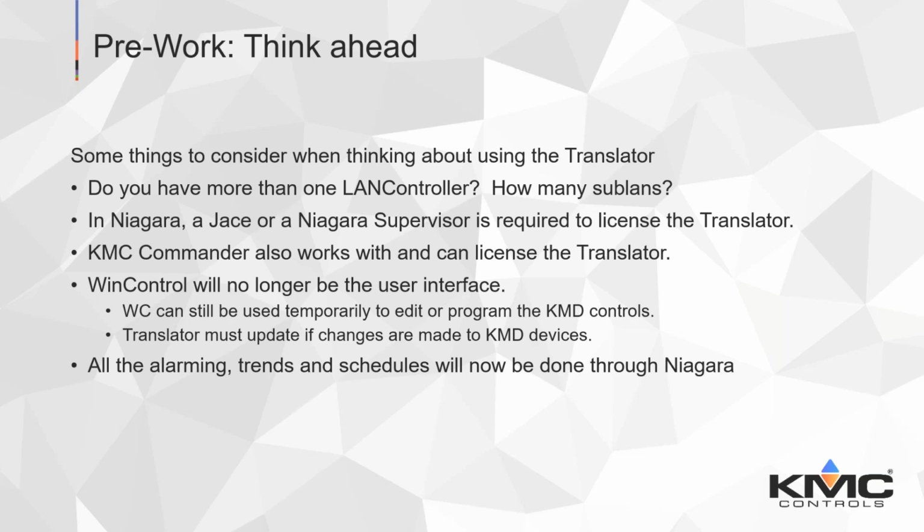So what you're saying is Win Control really becomes a technician's tool, not a user interface for the end user. That's right. All of the things you're using with Win Control, like your alarming, trends, and schedules, are all going to be done in Niagara now. So that all goes away in Win Control, and that's not something you can import. The translator imports the controllers and imports the points, but it's not going to import your trends, schedules, or alarms.